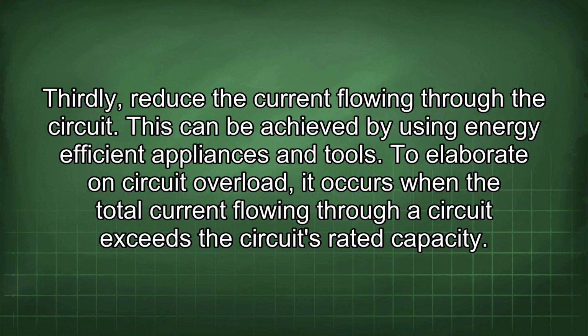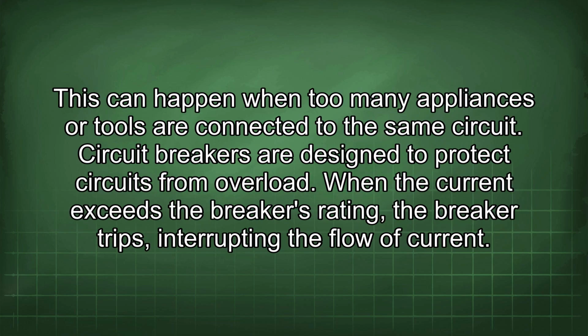To elaborate on circuit overload, it occurs when the total current flowing through a circuit exceeds the circuit's rated capacity. This can happen when too many appliances or tools are connected to the same circuit. Circuit breakers are designed to protect circuits from overload. When the current exceeds the breaker's rating, the breaker trips, interrupting the flow of current.